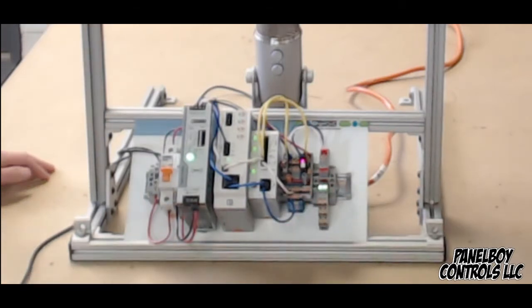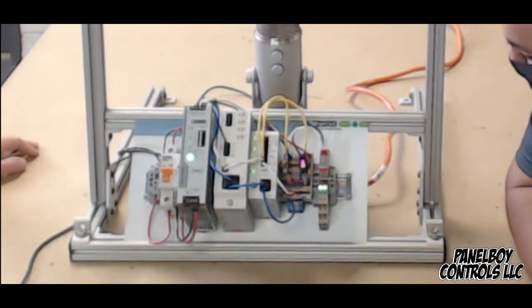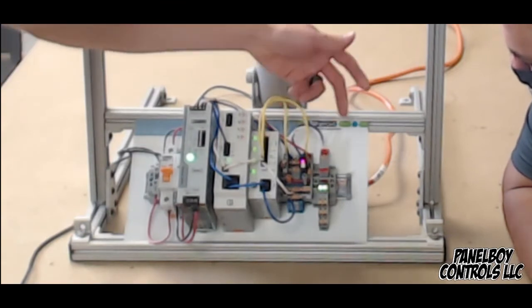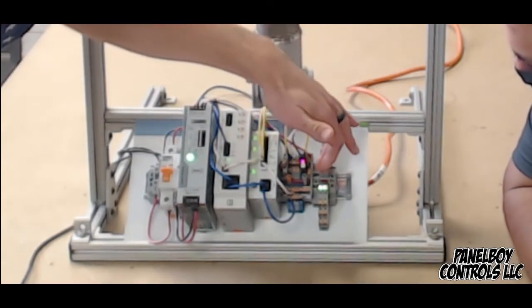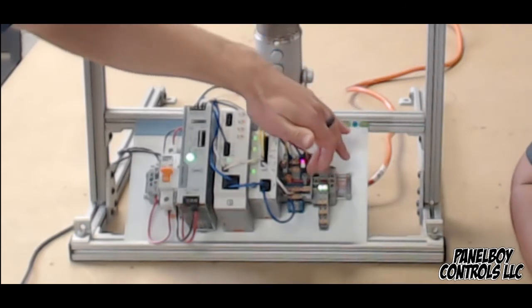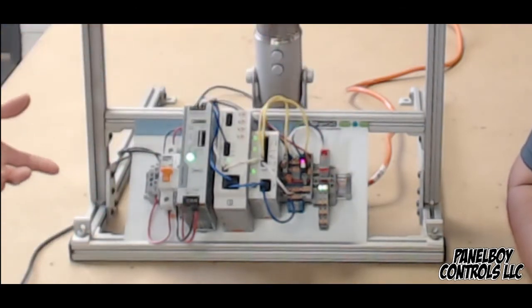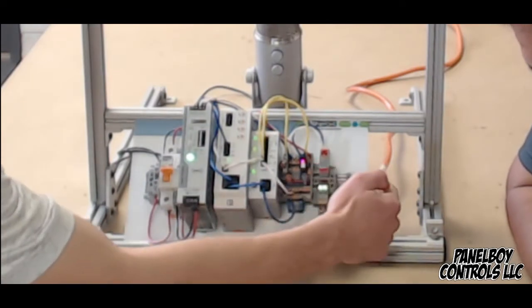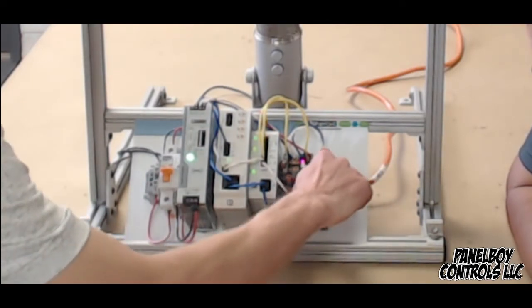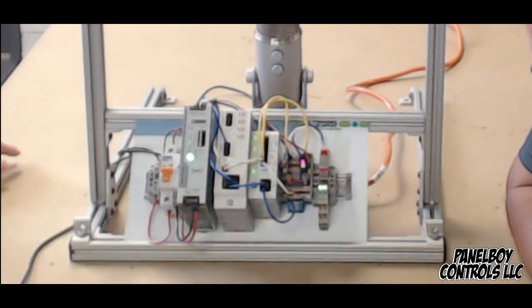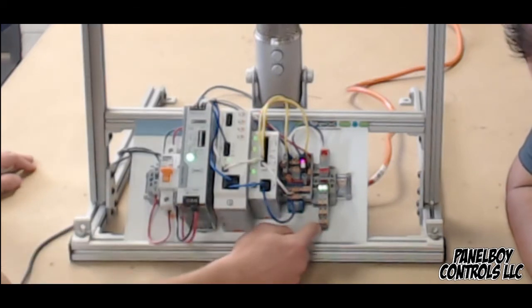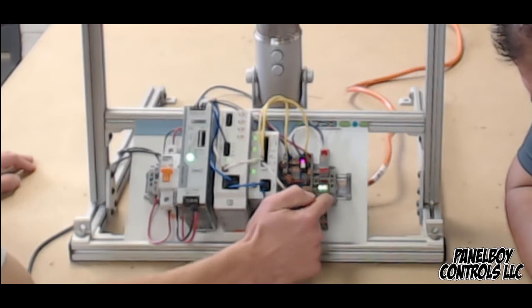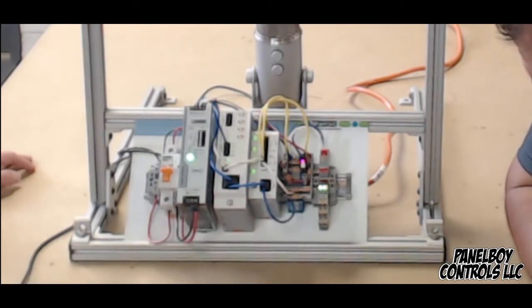This is a pretty well thought out product. It's meant for cases where maybe I've got a larger gauge wire that doesn't fit in there, and I can jumper from a larger gauge terminal block to this one. Likewise, if I want to protect larger gauge circuits, I can put protected circuit terminal blocks right there and jumper, because that terminal you see is tied to the protected circuit. This bottom terminal here is also a protected circuit, and there's a couple different things going on here too. I mentioned NEC class 2 before we started the show.